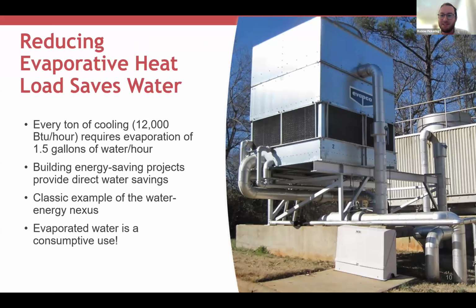I don't have a ton of time to dive into cooling tower operations and maintenance, but I want to provide a little bit of an overview just so you can understand that connection with fume hoods. Evaporation is the primary function of the cooling tower and is how the heat from the building and from equipment is carried away from the system. Based on the thermodynamics of water, 1.5 gallons of water per hour is needed to evaporate for every ton of cooling, and this number is pretty much fixed.